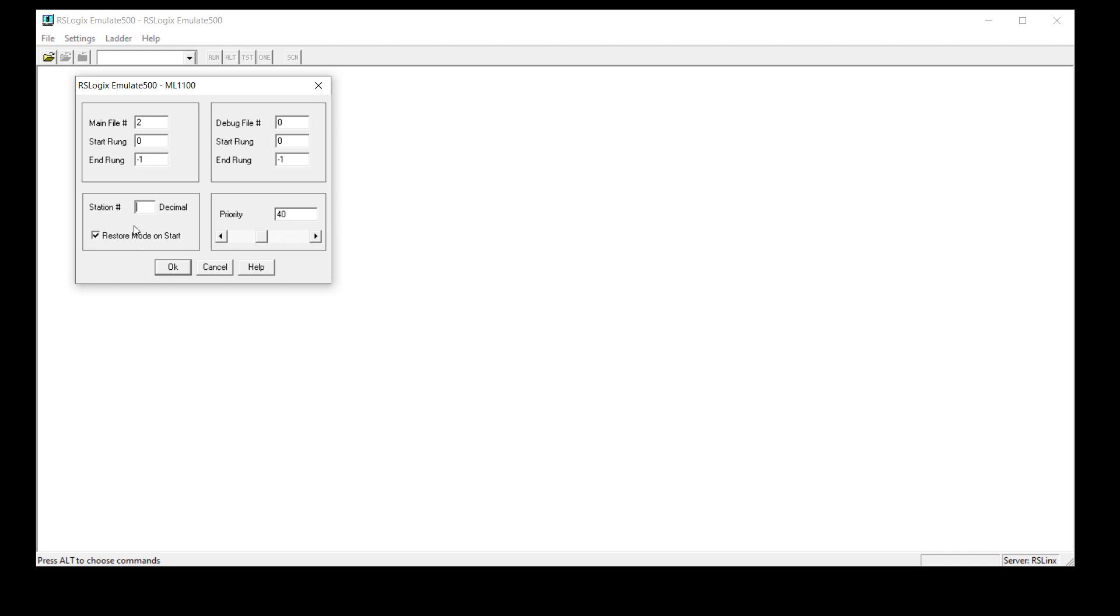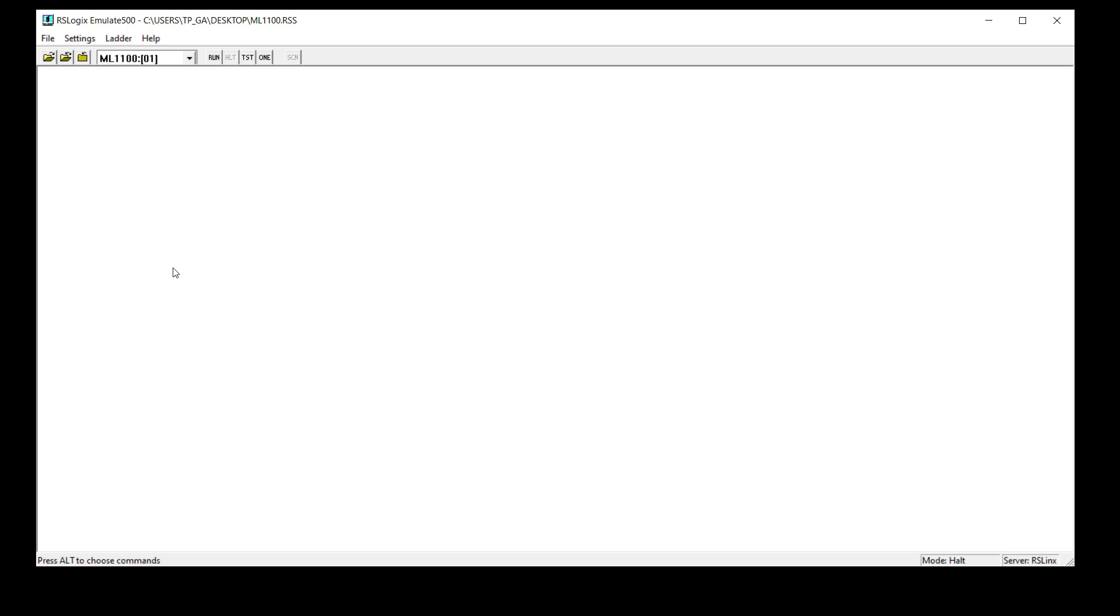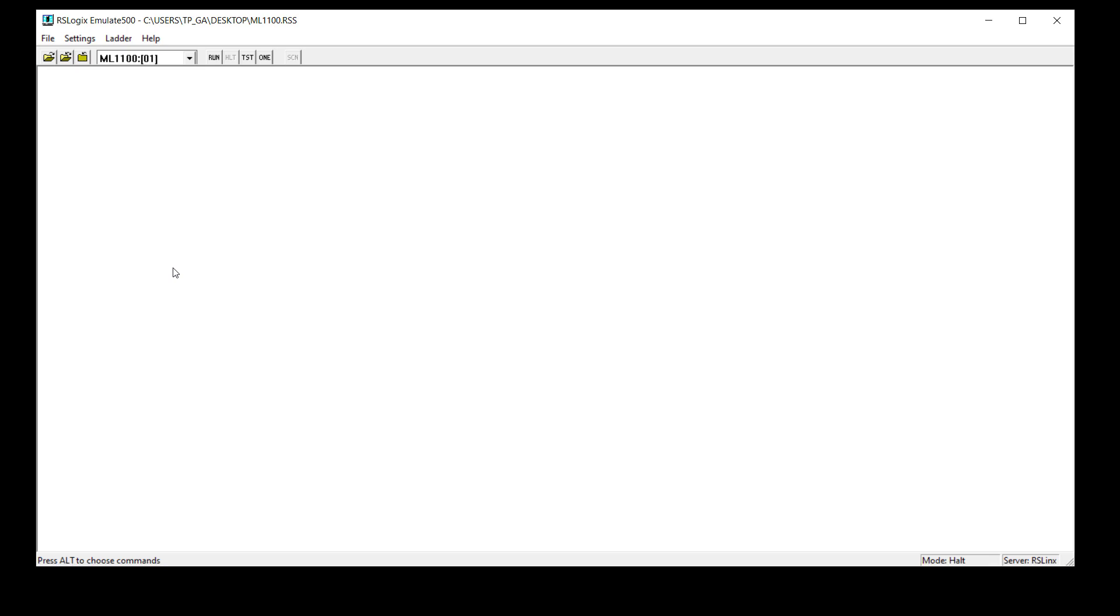Now we can assign a station number. One. Remember that your laptop or desktop was zero. So we'll assign this to station number one. And there are some things up there that you could change, but don't. Just leave it like that and then say OK. There's nothing really here to see much yet. But this emulation now has a personality. It looks like MicroLogix 1100 with no program in it. Because remember that we didn't create any program. We didn't create any rungs or anything or change anything. I just wanted you to see that you can start out with just a blank 1100.